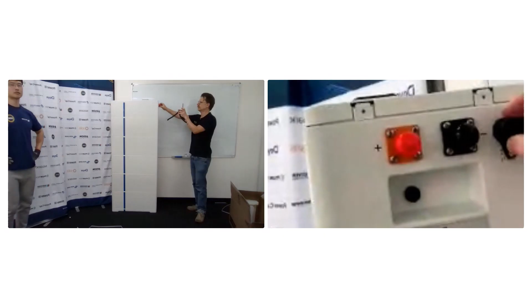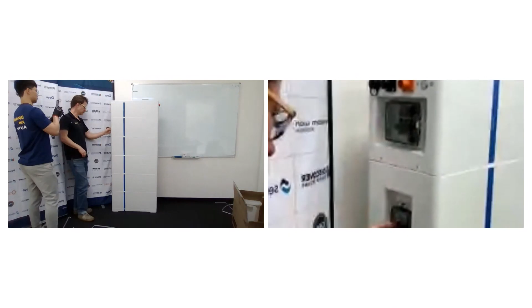So on this side we've got a positive and a negative and a comms connection here. We've got these two here, a little vent plug. And then over on the other side we've got the same thing, and an on-off switch, and a built-in breaker. And then each battery has a breaker on the side as well. These are here in case you want to have an additional stack, and they're just your standard Amphenol-style connector, which will bridge over to another stack.